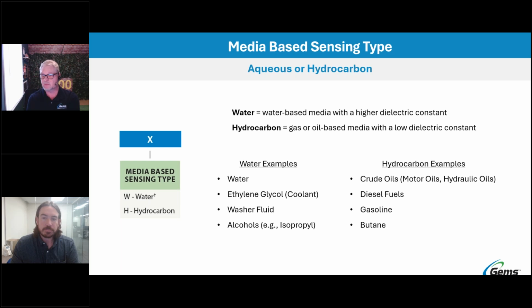Okay, next, and maybe one of the most important, is the media that you will be sensing. We have two different versions: the water-based version and what we call a hydrocarbon-based version. The water version is any water-based media with a high dielectric constant. You're talking your waters, your coolants, antifreeze, washer fluid, most alcohols. Those are all of the water-based liquids that'll have your high dielectric constants. The hydrocarbon, we just called it hydrocarbon for simplicity, but it is any crude oils, vegetable oils, for instance, fuels, gasoline, butane, liquid butane. Those are all hydrocarbon or oil-based examples.